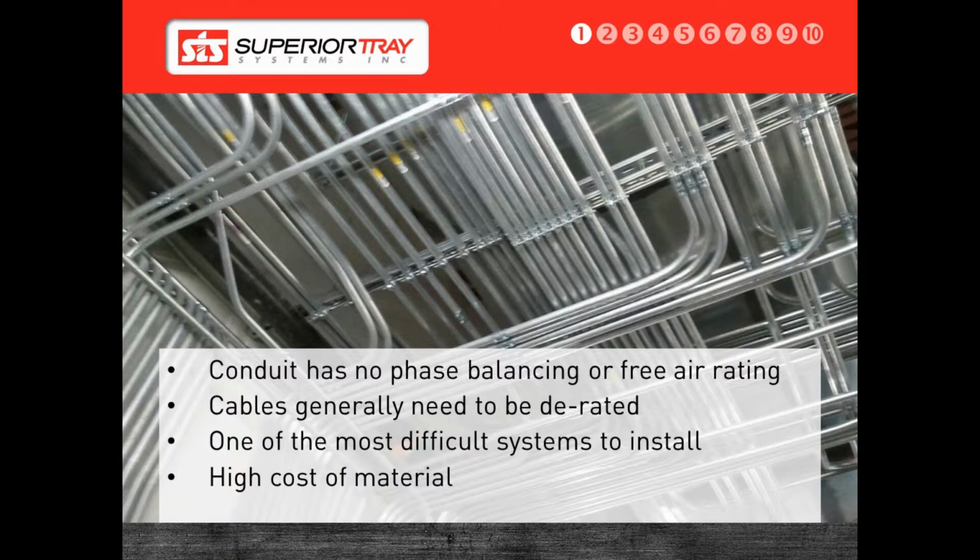In some industrial installations, like pulp mills and power plants, conduits can be a passageway for gas. Methane gas has been known to enter into conduits and travel down the conduit into switchgears, which may cause an explosion. This is an uncommon occurrence, but it has been known to happen.